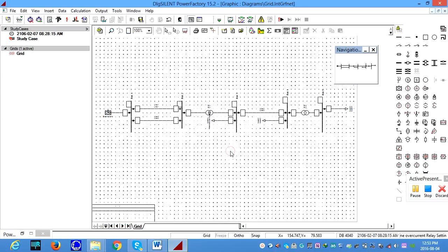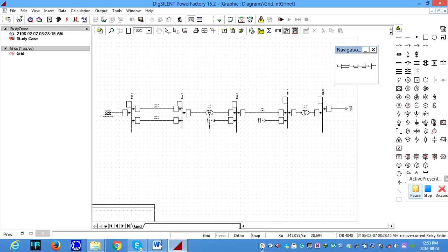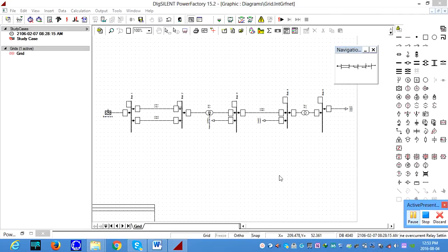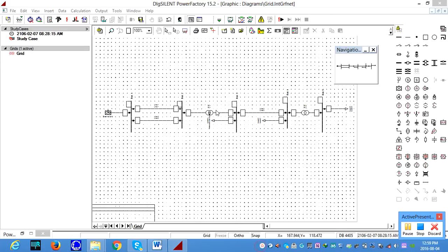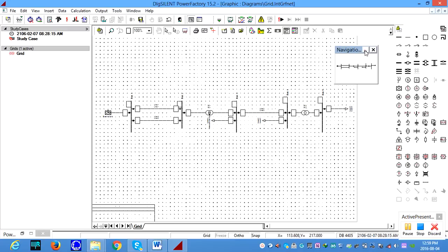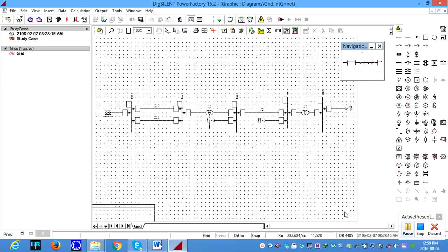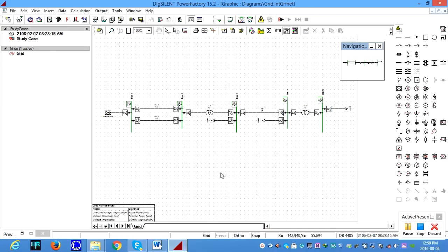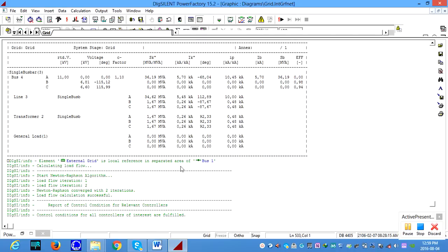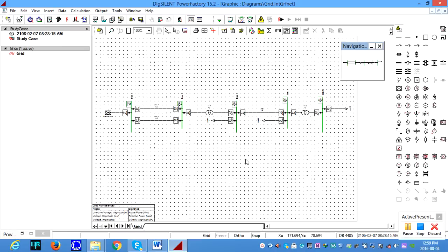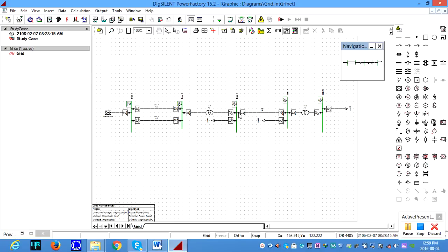Okay, so we are happy about that. The next step, we need to create the time overcurrent plot. After you set the protection relay settings, it's better to conduct the load flow again to verify. After you include the protection settings, the load flow is conducted successfully. Okay, you can see our load flow is conducted successfully after the protection settings. Now we need to validate the protection setting to verify.